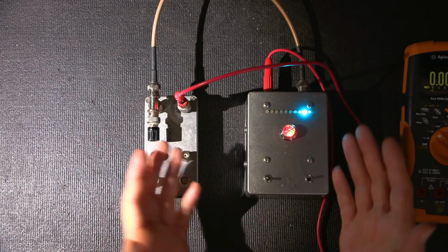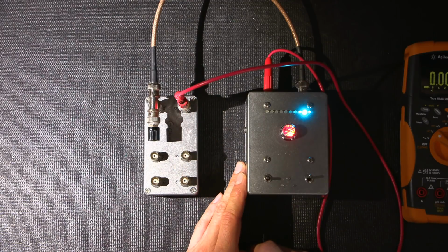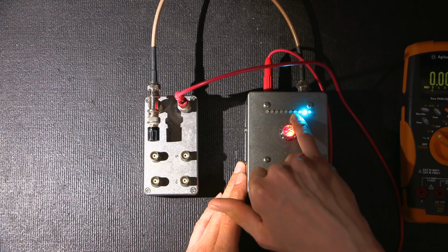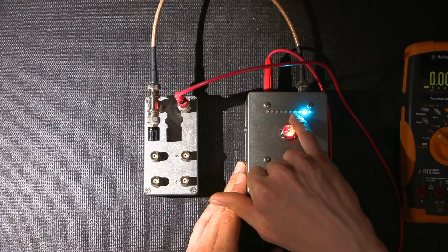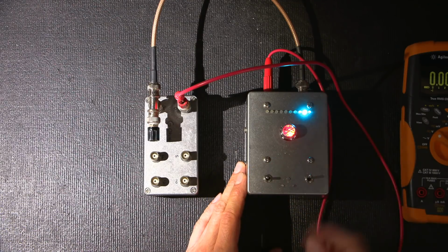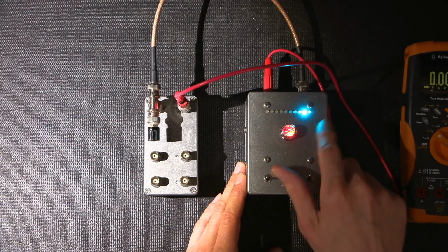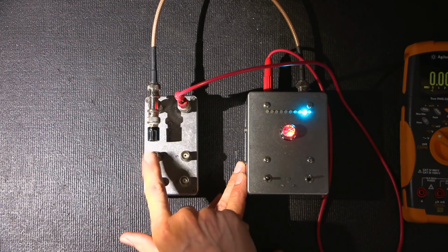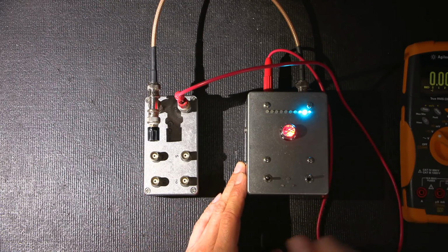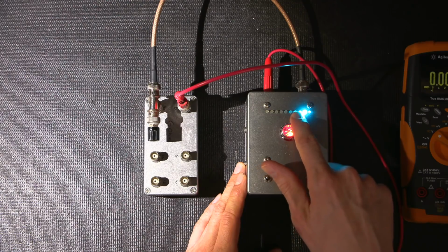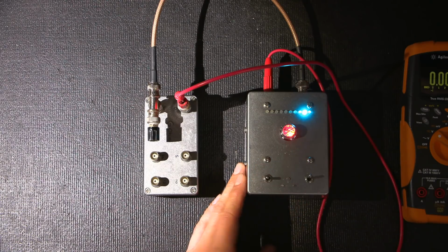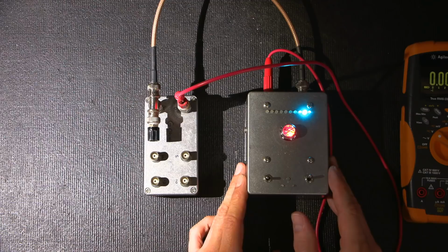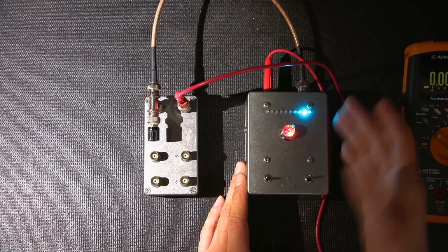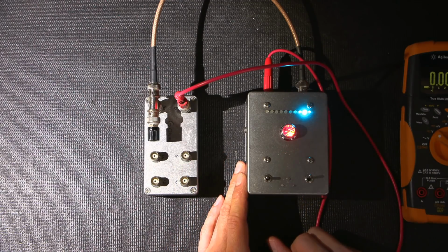And the alignment procedure, I'll just go over this quickly. If you're going to actually use a resistor array, you're going to want to align it to the fourth light, and after 10 minutes, it'll come down to the second. If you let the thing warm up for over 10 minutes, 10 to 15 minutes, you can align it to the second light on the 20 gig setting. Just because there are components in here that, as the unit itself gets warm, move just a little bit, and that will cause movement in the display here. So you'll want to align it for that second light after about 10 minutes. The best thing to do is wait for the 10 minutes. The bottom line is you get just a little bit more sensitivity out of the thing when it's cold.